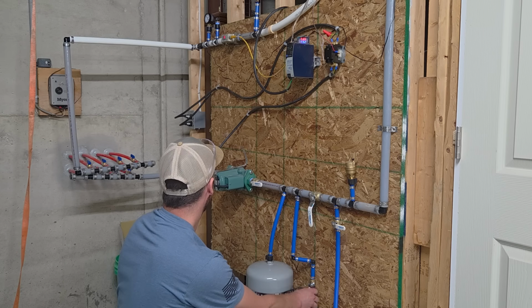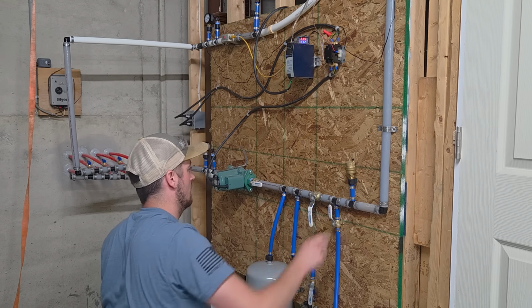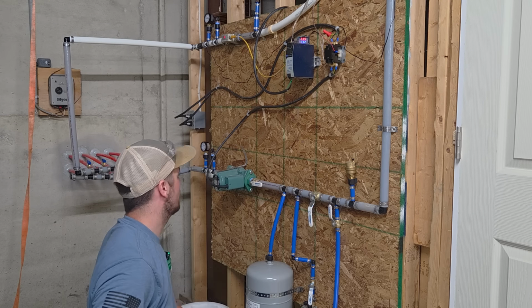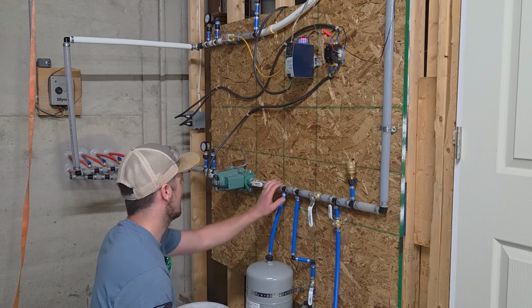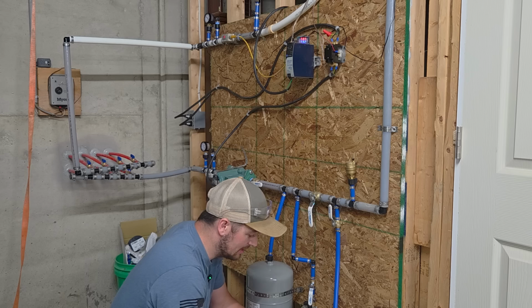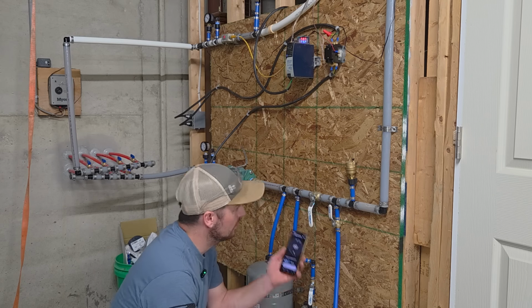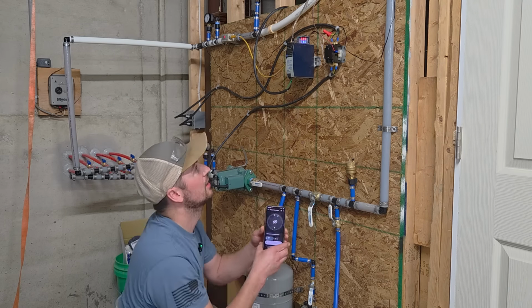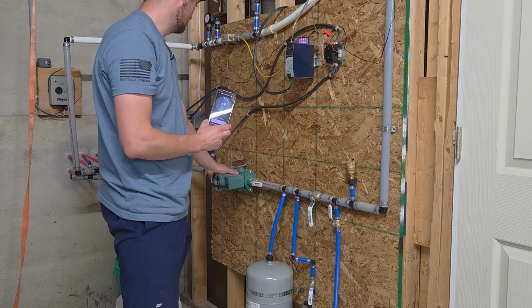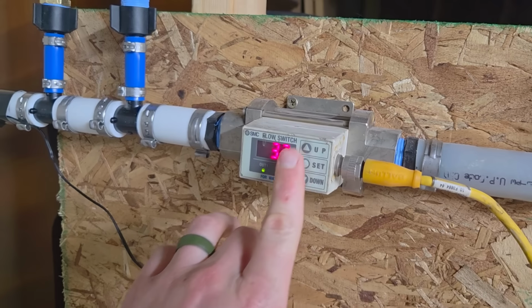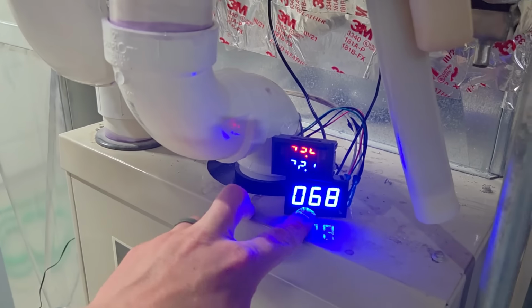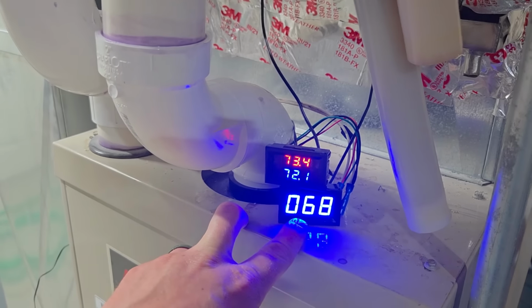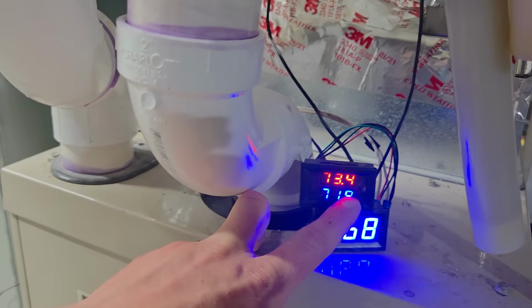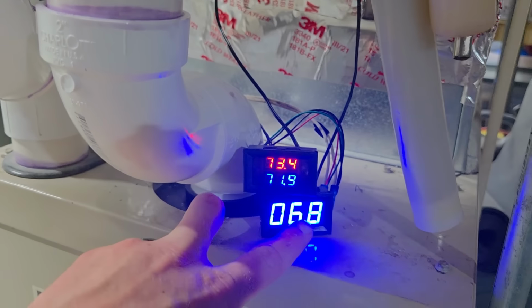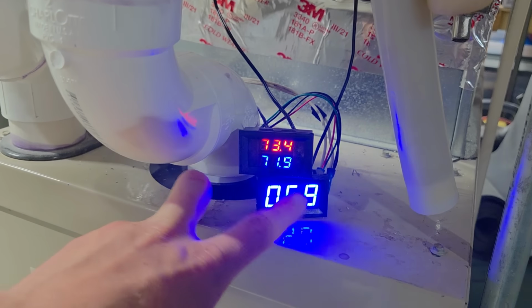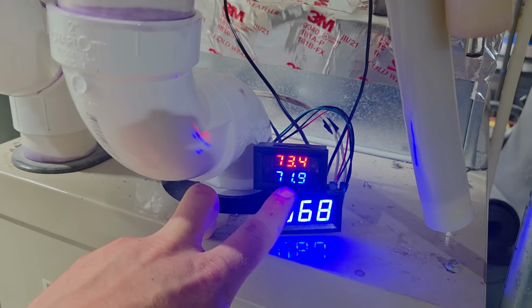So, and this is now flowing water through all 4 of the loops at the same time. I'm going to turn on the AC system on my thermostat. When I do that, my contactor kicks on, which supplies voltage to my water pump, 3.3, 3.2 gallons a minute. Our heat exchanger temperature dropped down to 68, hoping that goes quite a bit lower. The incoming air being 73.4, with a water temp of 68. My outgoing air temperature is 71.9.